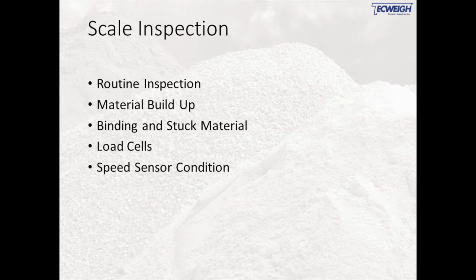It's always a good idea to do a routine inspection when you do a calibration. Check for material buildup, any binding or stuck material. Make sure the load cells are free of movement, and also check the speed sensor as well. Make sure it's not bouncing or it's jammed up somewhere or getting too much material forming on it. It's always a good idea to do that visual inspection regularly. That'll help avoid problems.